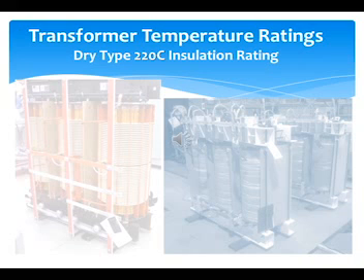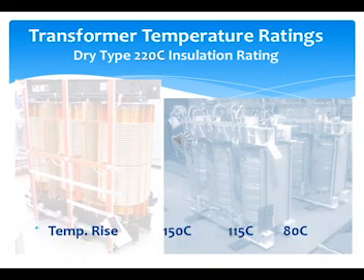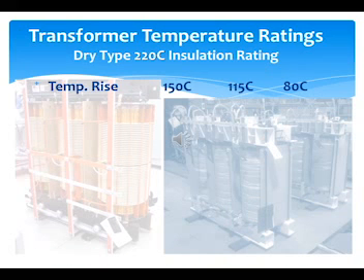Dry type transformers typically have insulation systems rated for 220 degrees C. The ANSI standard allows us to add the elements together so as to compare designs and ratings easily. Temperature rise is one important consideration. With a 220C insulation system, it's important the transformer not exceed 220 degrees C.